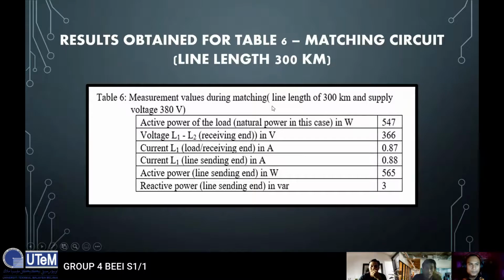Okay, for table 6, for line length 300 km, the active power of load, natural power in this case, is 547 watt. Voltage line 1 to line 2 at the receiving end is 366 volt. For current line 1 at the receiving end, 0.87 ampere. For current line 1 at the sending end, 0.88 ampere. For active power at the sending end is 565 watt, and reactive power at the sending end is 3 var.